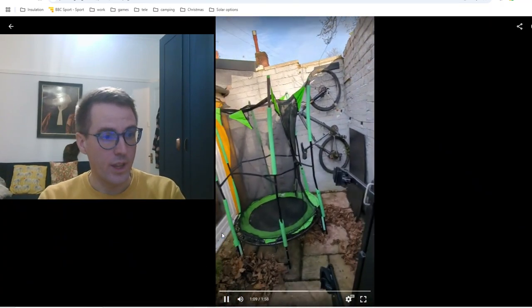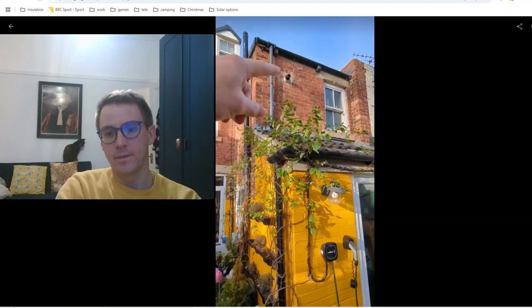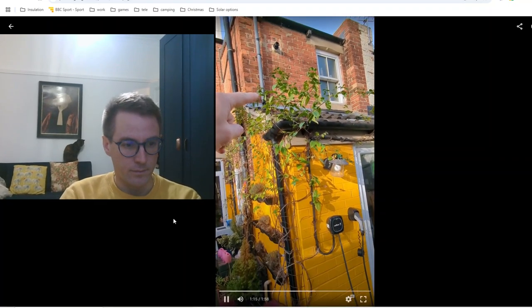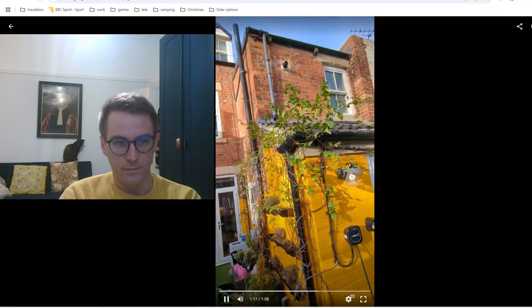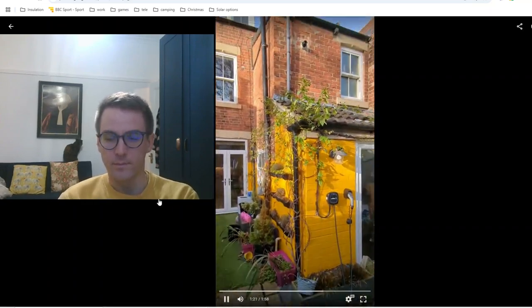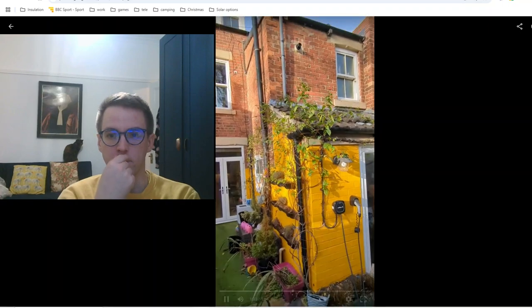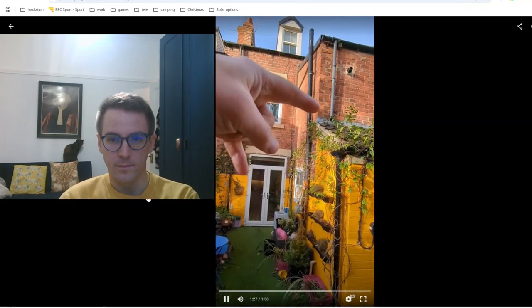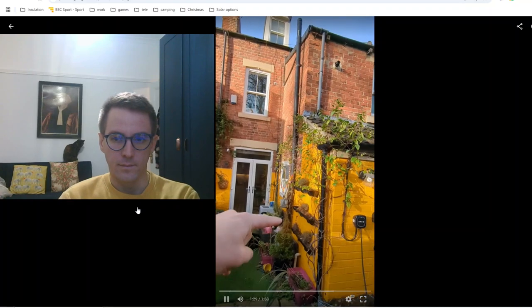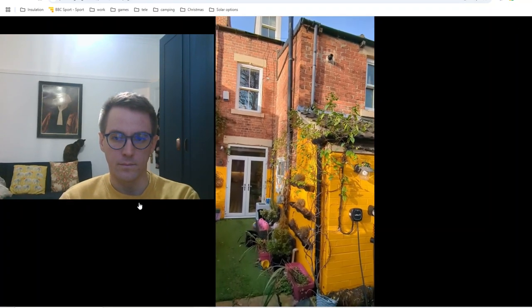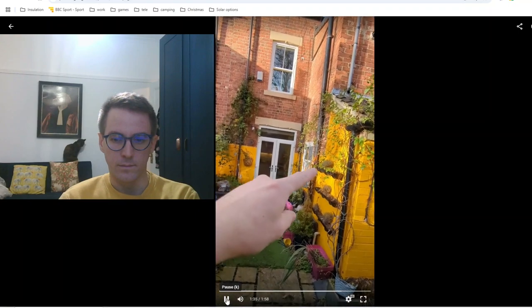Right, we're zoomed again. Take off the primaries up to the boiler here, and because we'll have around a 10 kilowatt heat pump, we should be able to run it through our 22 mil primaries, because we'll have a 22 coming down to the ground floor and doing that separately, and another 22 going up to the middle and top floor. And so we've got a 5 kilowatt heat loss here.